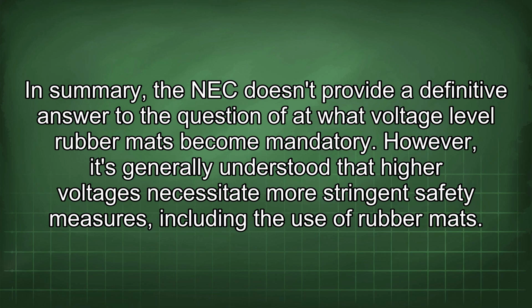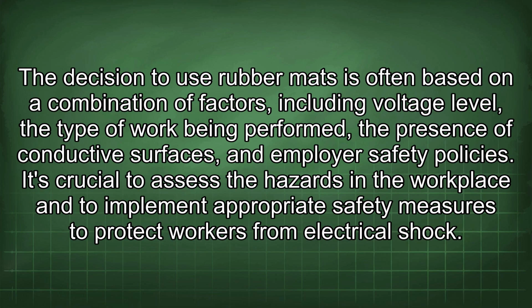In summary, the NEC doesn't provide a definitive answer to the question of at what voltage level rubber mats become mandatory. However, it's generally understood that higher voltages necessitate more stringent safety measures, including the use of rubber mats. The decision to use rubber mats is often based on a combination of factors, including voltage level, the type of work being performed, the presence of conductive surfaces, and employer safety policies.